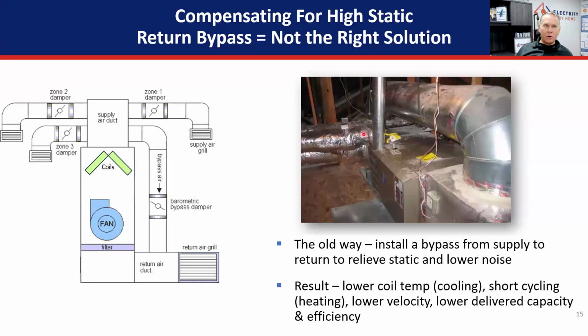I bring it across the coil. I now have 55-degree air, ish, going into this plenum if my static pressure is right. And then I'm going to blow 55-degree air back into the return. That's going to lower my return air temperature dramatically, which could drop the coil temperature below freezing. That's the problem we saw with these things all the time. They still cause the unit to freeze up because the return air temperature got so cold. And in the winter time when you're running the furnace, it was even worse.